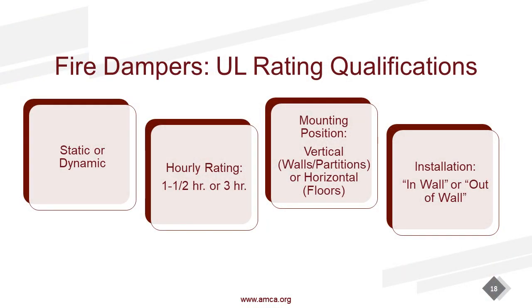I need to understand what the hourly rating of my barrier is, right, to determine what the rating of my damper needs to be. Where am I putting this damper? Am I putting it on a wall or am I putting it on a floor? And one we don't often consider is access and service and testing. Can I get to the damper to do these things? Sometimes we need what's called an out-of-wall damper, and I'll go into that in more detail.